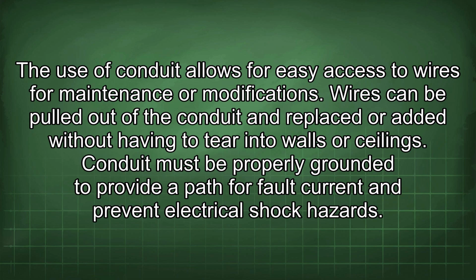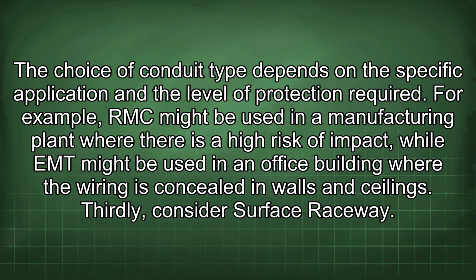Wires can be pulled out of the conduit and replaced or added without having to tear into walls or ceilings. Conduit must be properly grounded to provide a path for fault current and prevent electrical shock hazards. The choice of conduit type depends on the specific application and the level of protection required. For example, RMC might be used in a manufacturing plant where there is a high risk of impact, while EMT might be used in an office building where the wiring is concealed in walls and ceilings.